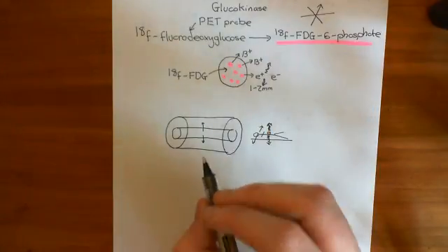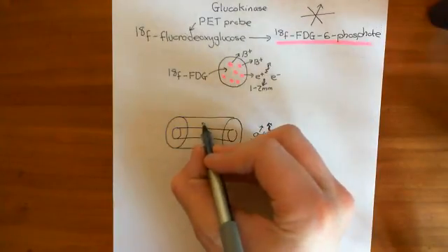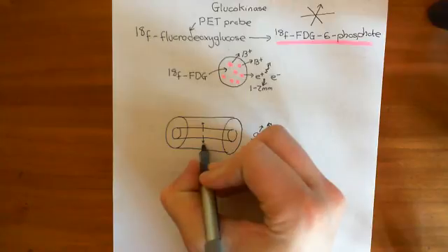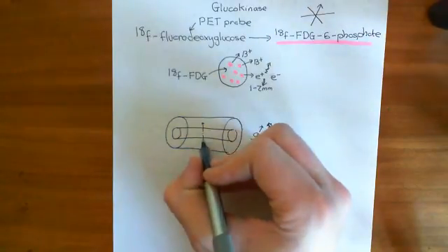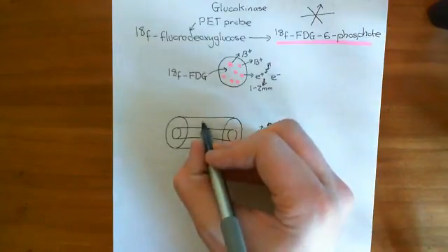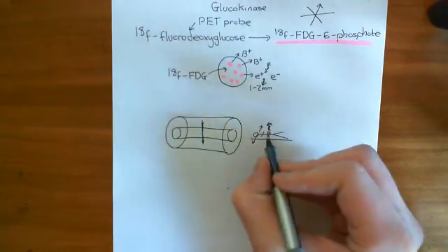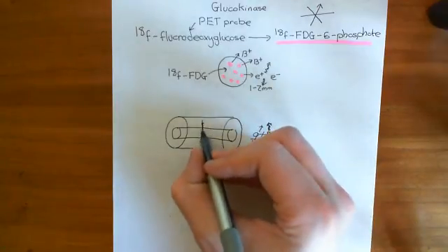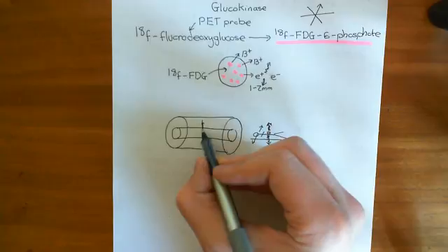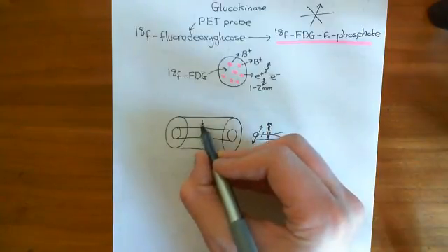What the detector will do is it will detect the photon arriving up here. It will detect the photon arriving here. And then it knows that somewhere in that line, somewhere in that vertical line, a positron and an electron annihilated it. So it roughly knows the position.